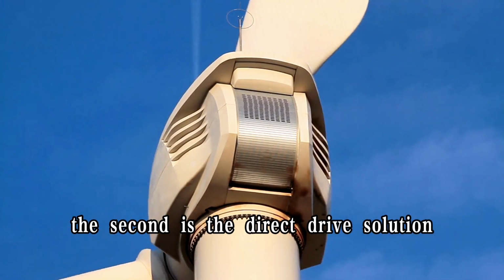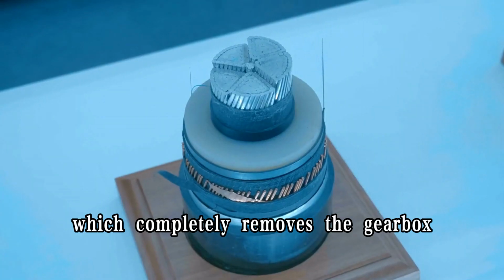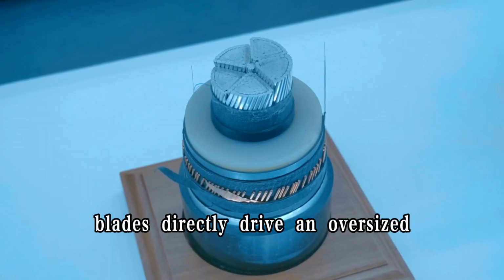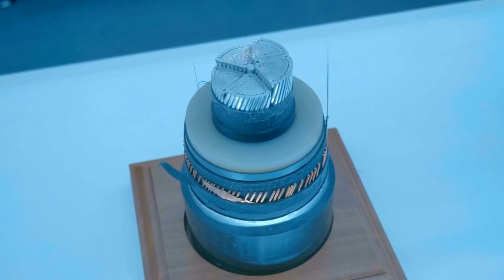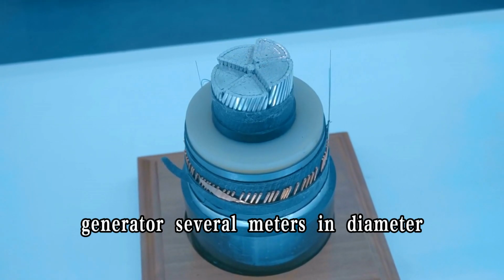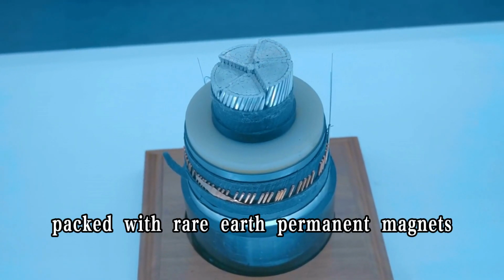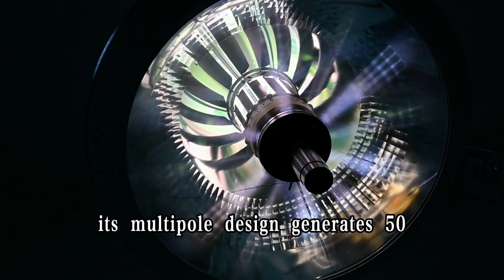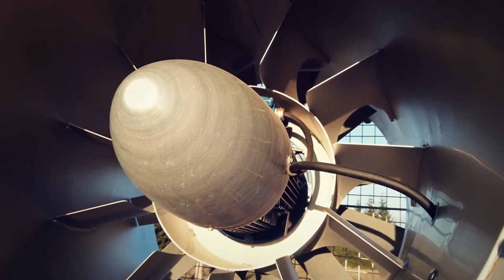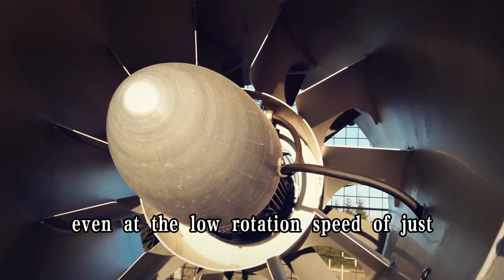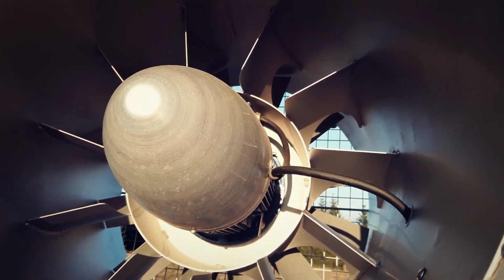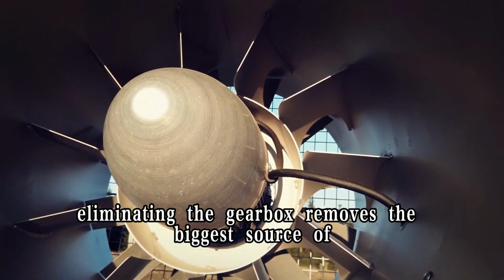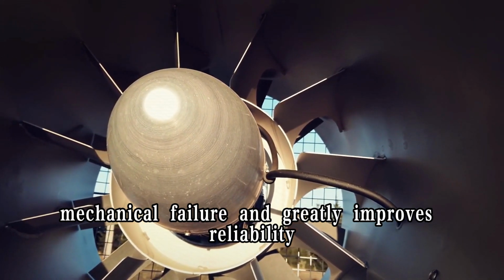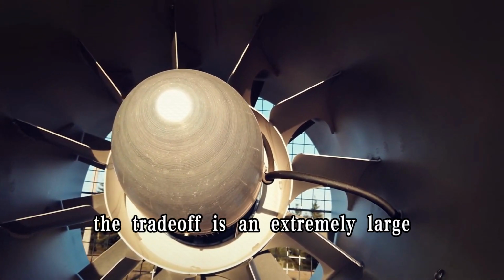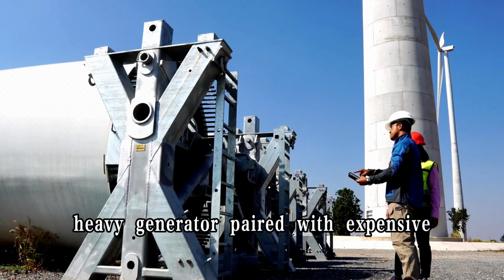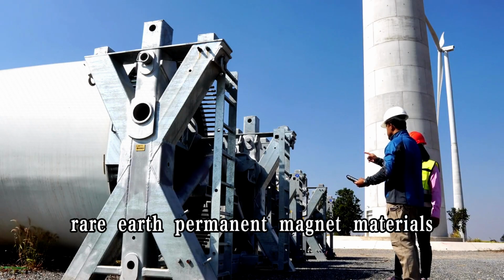The second is the direct drive solution, which completely removes the gearbox. Blades directly drive an oversized low-speed permanent magnet generator several meters in diameter, packed with rare earth permanent magnets. Its multipole design generates 50 Hz alternating current directly, even at the low rotation speed of just over 10 revolutions per minute. Eliminating the gearbox removes the biggest source of mechanical failure and greatly improves reliability. But the trade-off is an extremely large, heavy generator paired with expensive rare earth permanent magnet materials.